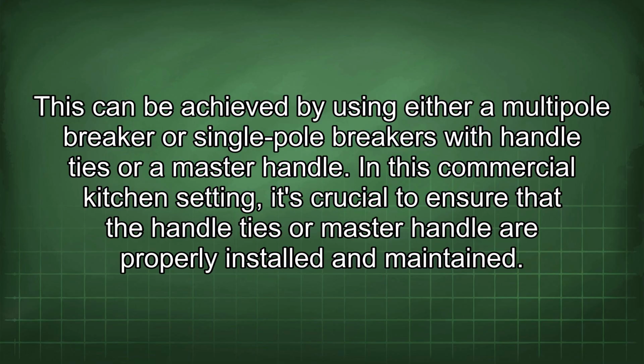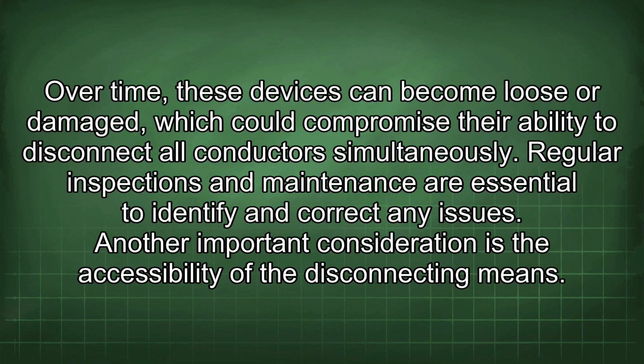In this commercial kitchen setting, it's crucial to ensure that the handle ties or master handle are properly installed and maintained. Over time, these devices can become loose or damaged, which could compromise their ability to disconnect all conductors simultaneously. Regular inspections and maintenance are essential to identify and correct any issues.